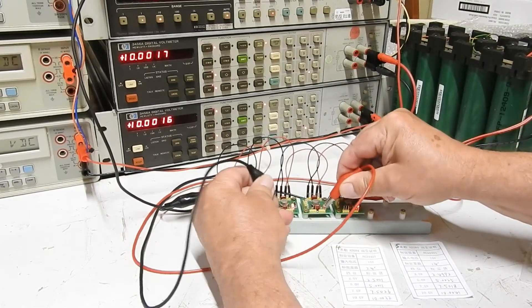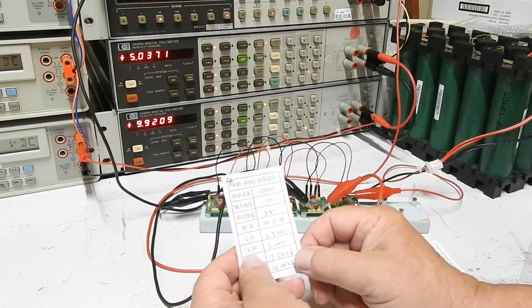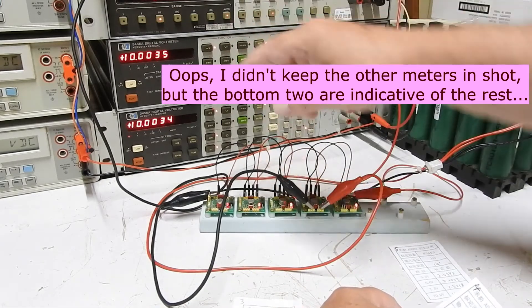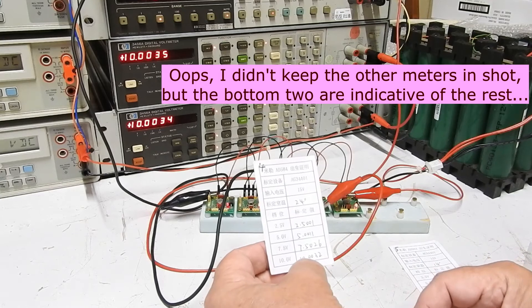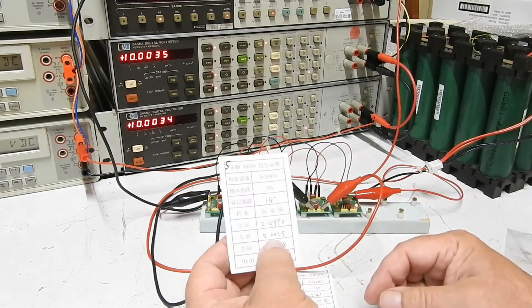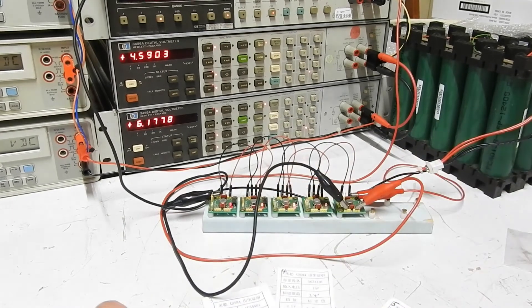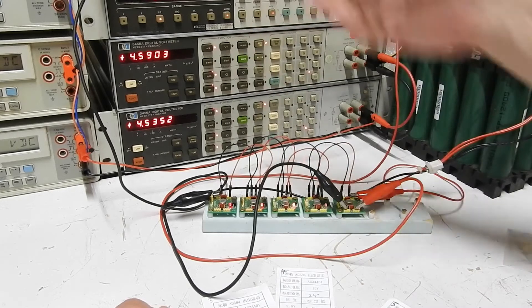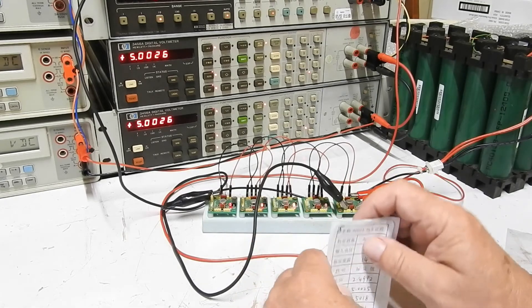which is also set to 10 volts. We'll let those average up over time. It should be 10.0032, and you'll see that they're all close to that, although reading a little high now. And the third one is set to 5 volts currently, so that should be 5.0025. Again, within 200 microvolts. Not that the accuracy of those things is important for this, but just that they be stable, and you can see that these four are always in pretty good agreement, and those ones are all over the shop.